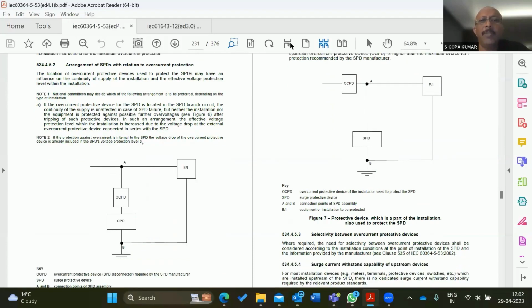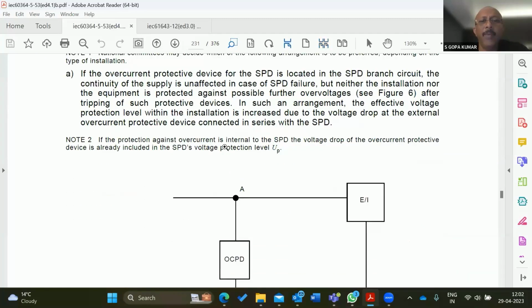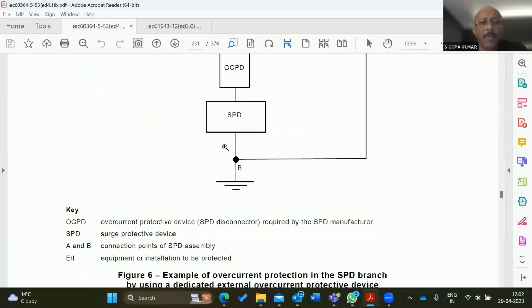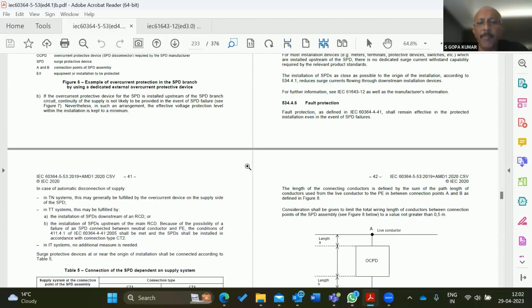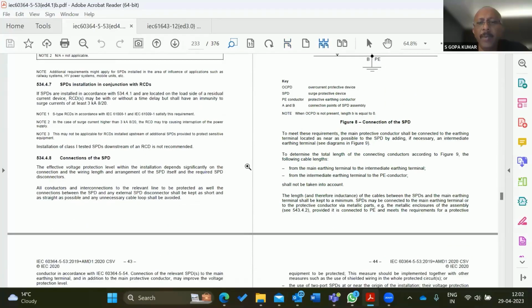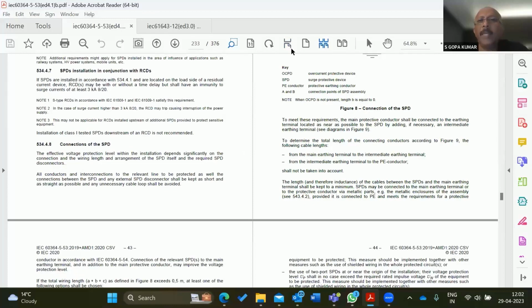Now, as Mr. Vijay was explaining, continuity of supply and continuity of protection. SPD has to be selected based on continuity of supply or continuity of protection. The question is whether you need protection at the end of life of the SPD, or you need the power supply without interruption at the end of the life of the SPD. These are very much included in the latest standards.